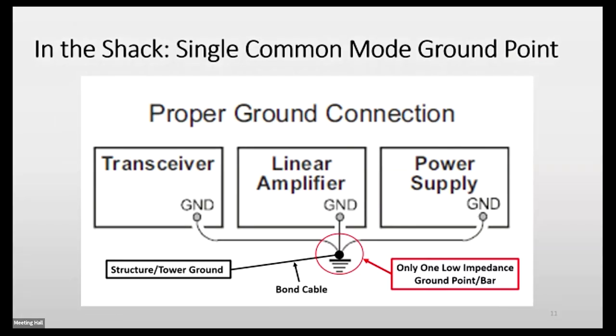Create a single mode, common mode ground point. Get everything to a single point with as short a cable as possible, and tie that to your structure tower ground. You want these cables as low as you can so it's a low impedance point to tie together. People say, well I've got coax and it's all grounded together. Yeah, that's true, but the equipment chassis is not grounded through the coax. Take a DC meter, it is, but from an RF standpoint, it's not. So you do need that ground in there if you want a lower impedance connection and get your common mode issues taken care of.